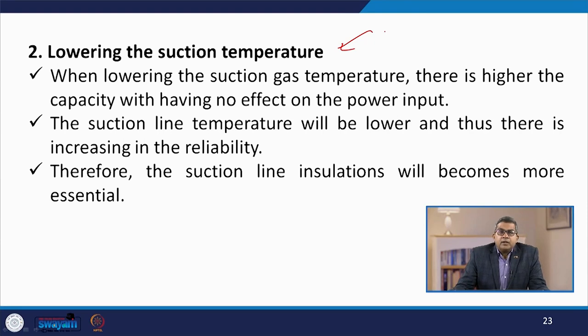Another approach to altering compressor efficiency is lowering the suction temperature. When the suction gas temperature is lowered, there is higher capacity with no effect on power input. The suction line temperature will be lower, increasing reliability; therefore, suction line insulation becomes more essential in that case.